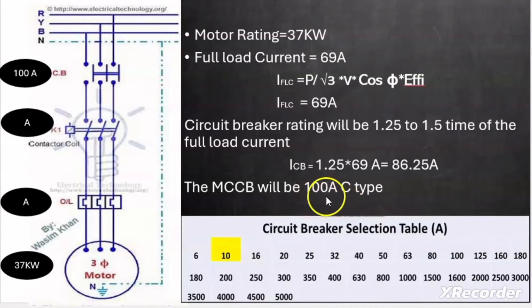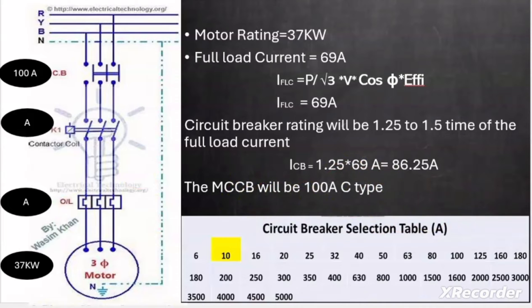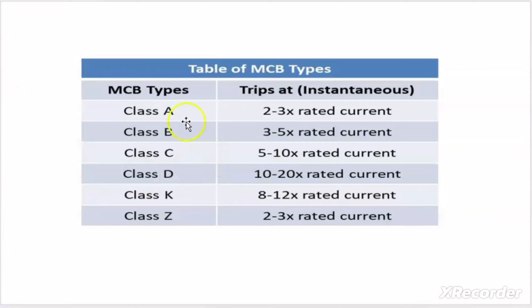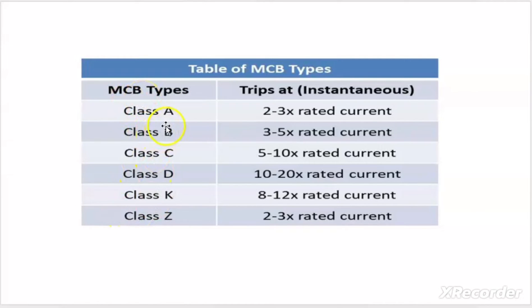Apart from the 100 ampere rating, I also specified C type for the MCCB. MCBs and MCCBs come in different types: class A, class B, class C, class D, class K, and class Z. These are called curve ratings of the circuit breaker, and this rating is very important. The curve rating allows the MCCB or MCB to not trip at the time of starting even though the current exceeds the rated current.